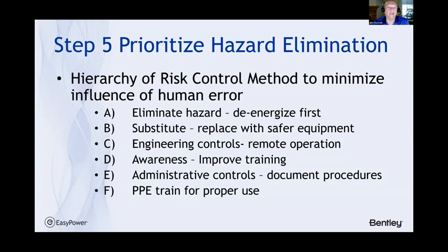These days, it's recognized that there can be an order of hazard elimination if we follow this hierarchy method. And the first step is to eliminate the hazard, which primarily is de-energization as a first step. And then substitute with safer equipment. There's technology now for trip units that can be adjusted or set to operate quicker or faster during a work in process situation, so that personnel are exposed to a lower hazard, including this technology.